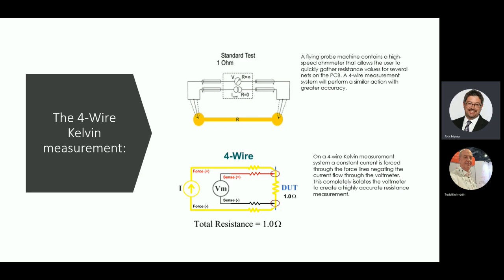The lead resistance is neglected in this case. So it's automatically reduced to zero. So you're going to get the true value of the component. This happens both on the red side or the positive side, and the black side, the negative side of the reading. So if you truly have a 1 ohm resistor and you know that's good and it's come from the manufacturer plus or minus 0.1%, so you know for sure that this resistor is 1 ohm. So you put the 4-wire Kelvin on there, you're for sure going to read 1 ohm because of the way that the calculation works, as Todd mentioned earlier today, that it reduces the lead resistance to 0, makes it negligible. So you get very, very accurate, very, very fine measurements. Now, 4-wire Kelvin works best below 1 ohm, but also works at any level of resistance.